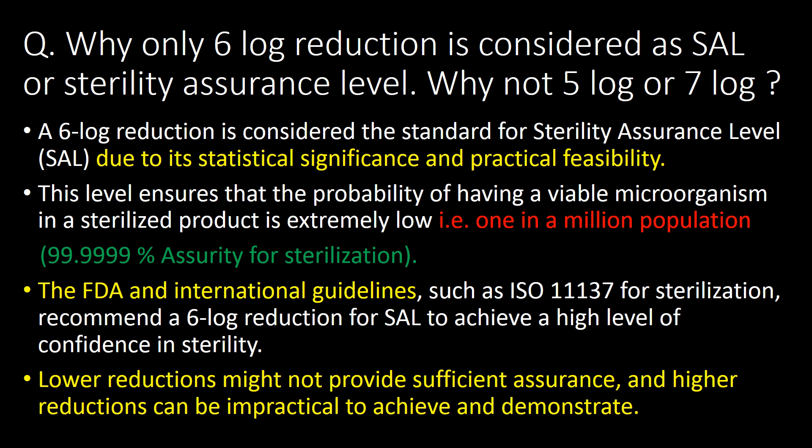It is practically feasible to achieve 6 log reduction with commonly used sterilization methods — that is, dry heat sterilization, moist heat sterilization, and radiation sterilization. This level ensures that the probability of having a viable microorganism in a sterilized product is extremely low, that is 1 in a million. With 6 log reduction, we will be assured 99.9999% sterility.